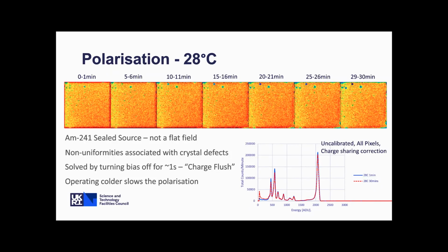But that's very easily recovered. So all we have to do to stop this happening is turn the bias off the detector for about 1 second. And this is just what we call a charge flush, and it happens automatically in the software. It's something that's taken care of for the user, but just something to be aware of.